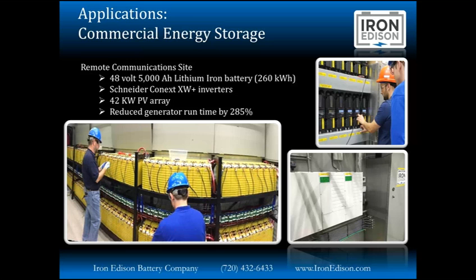Because of the size of the battery and the size of the solar array, we've actually been able to reduce generator runtime by 285%. This is a huge battery, 260 kilowatt hours of total capacity. We have 2 Schneider XW Plus inverters. And the great part about using Schneider in this application is the fact that they're safe and designed to operate in the positively grounded environment that's required by a telecom application.